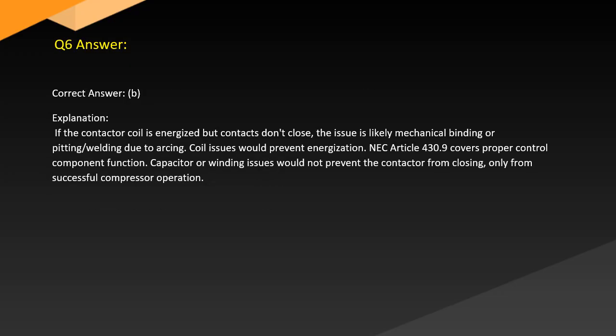Answer. Correct answer: B. Explanation: If the contactor coil is energized but the contacts don't close, the issue is likely mechanical binding or pitting and welding due to arcing. Coil issues would prevent energization. NEC Article 430.9 covers proper control component function. Capacitor or winding issues would not prevent the contactor from closing, only from successful compressor operation.